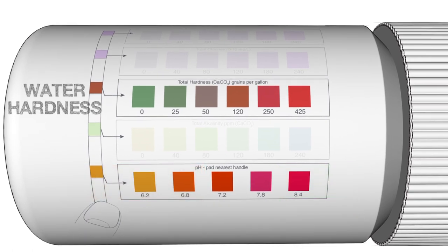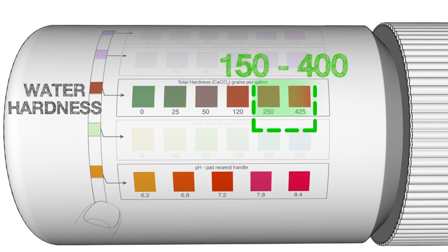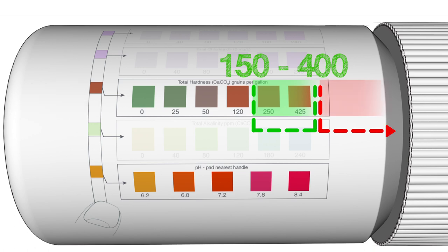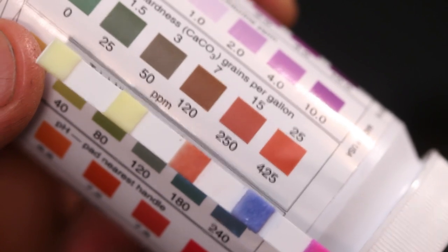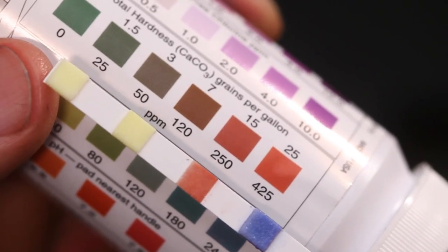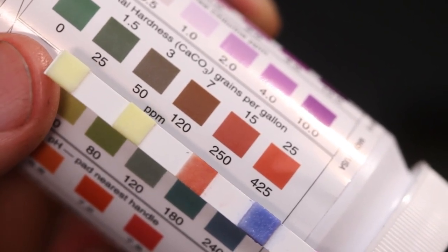A water hardness reading between 150 and 400 parts per million is acceptable for most coolants. Readings above this range also increase the chance of corrosion and bacterial contamination. And separation of the water and concentrate becomes more likely as water hardness becomes excessive.